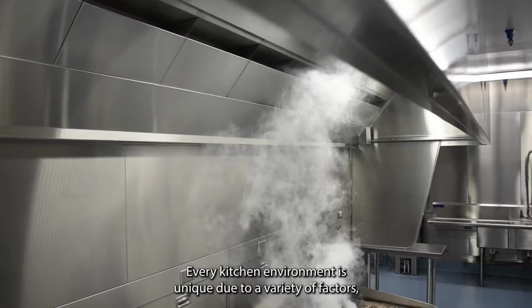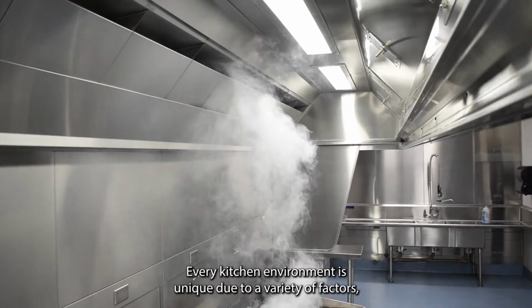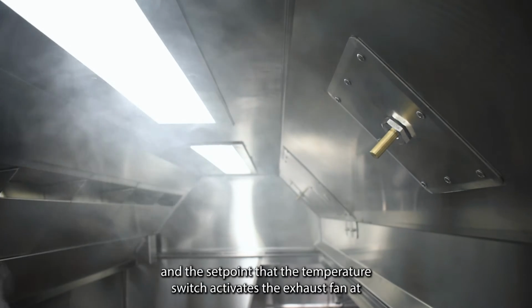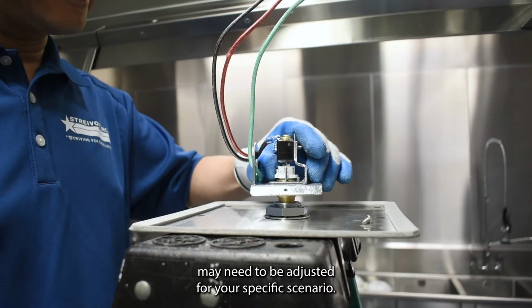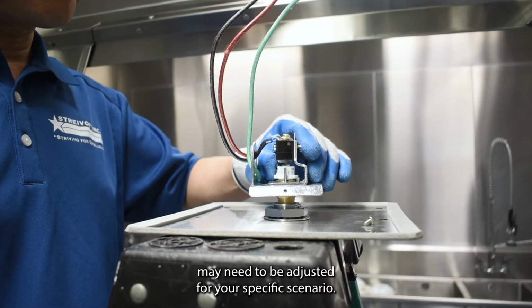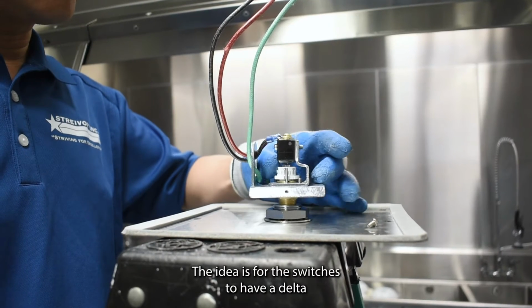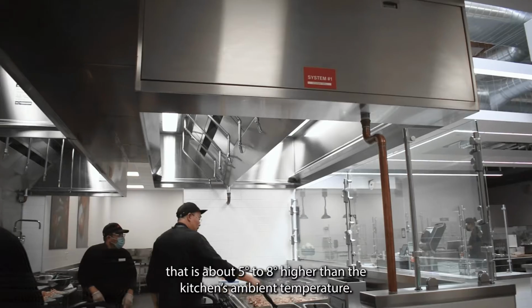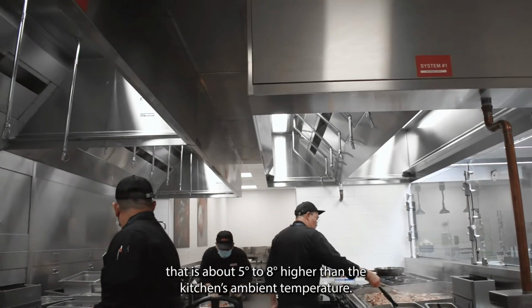Every kitchen environment is unique due to a variety of factors, and the set point that the temperature switch activates the exhaust fan at may need to be adjusted for your specific scenario. The idea is for the switches to have a delta that is about 5 to 8 degrees higher than the kitchen's ambient temperature.